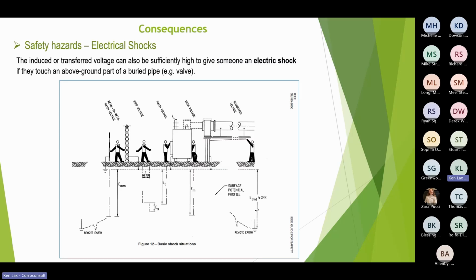And those test posts typically are connected to the pipe via this cable, via a stud, which is accessible from the outside of the test post. So the technician can just walk up, stick his probe on the stud and his widget in the ground and get a reading and see how things are. Well, if you're in an area which is at risk for electric shock, then these test posts have to be changed to make sure you can't touch them from the outside.